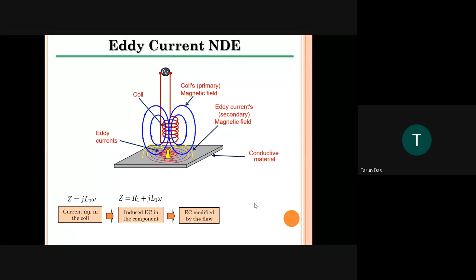This is the eddy current. The variation of magnitude and phase of this eddy current signal will generate a secondary magnetic field that will oppose the primary magnetic field. Then, if some defect or discontinuity comes in the flow of eddy current, the impedance of the coil will be modified, and the discontinuity will be represented as the impedance change of this coil. The variation of magnitude and phase is monitored using a search coil, or the same coil, by measuring the change in current or impedance of the primary coil.